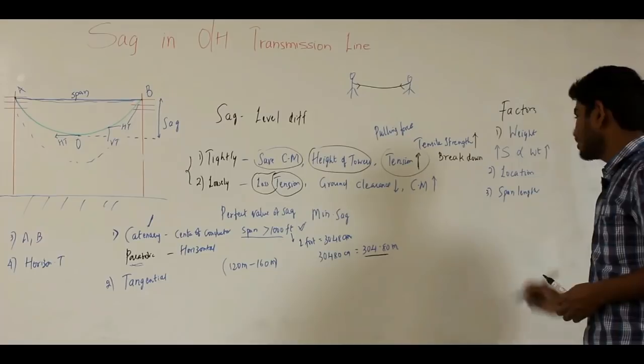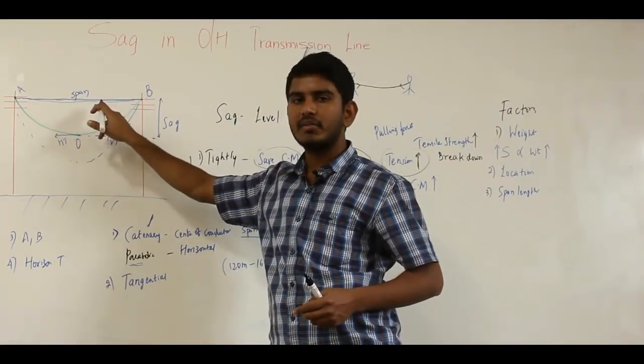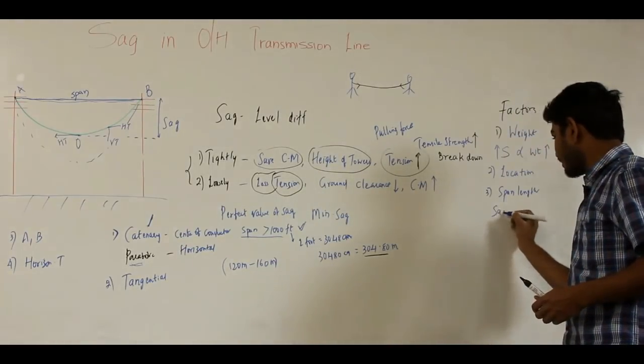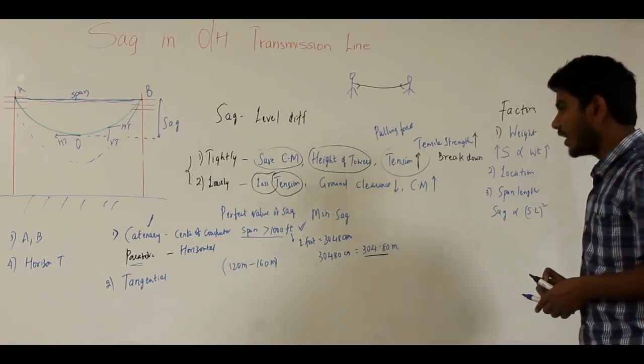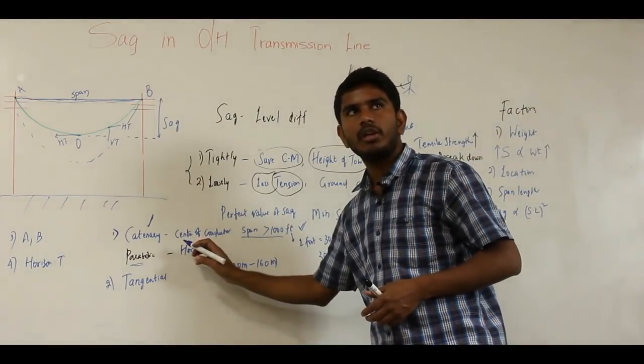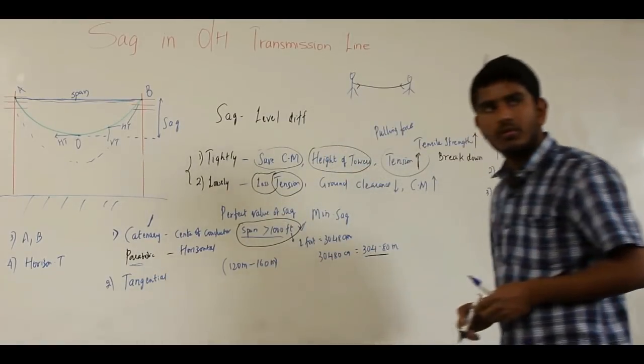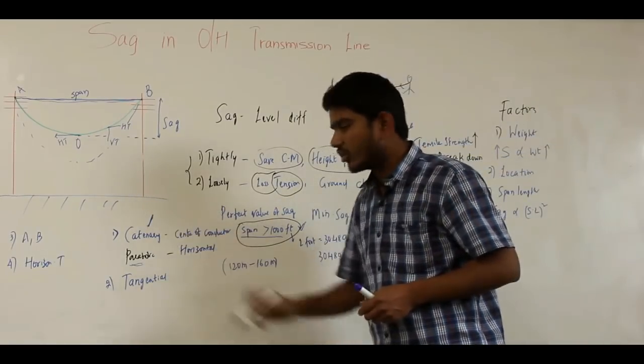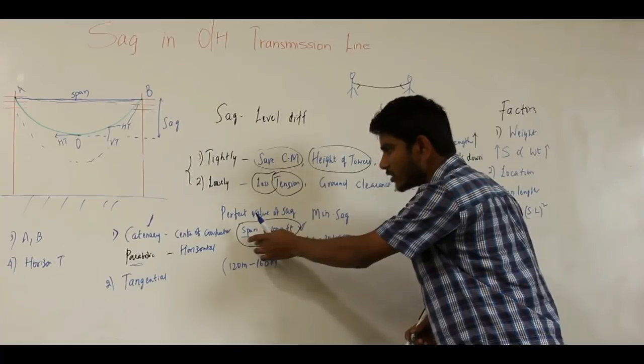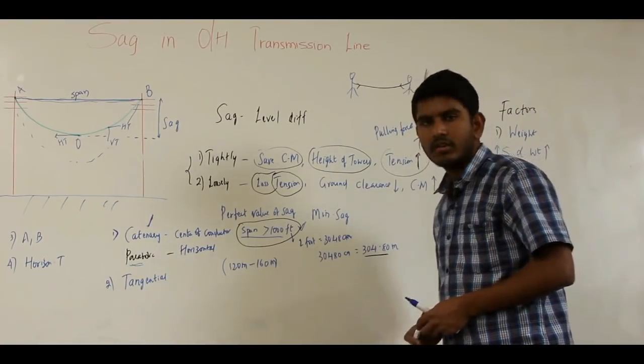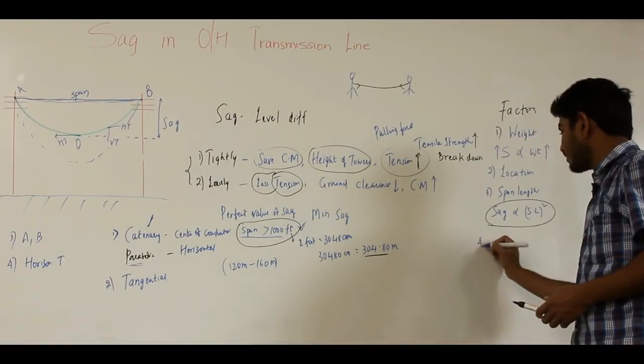The span length also affects sag: more span length means more sag. Sag is proportional to the square of the span length. For greater span lengths (above 1000 feet), the catenary curve gives more accurate results; for lesser span lengths, a parabolic curve is used. Temperature is another factor: as temperature increases the conductor expands and sag increases, while as temperature decreases the conductor contracts and sag decreases. Sag is proportional to temperature. The fifth factor is tensile strength, which is inversely proportional to sag — more tensile strength means less sag. The sixth factor is tension, which is also inversely proportional to sag.